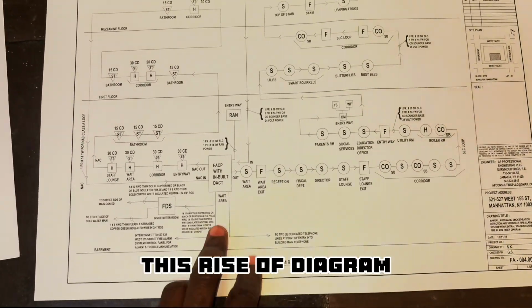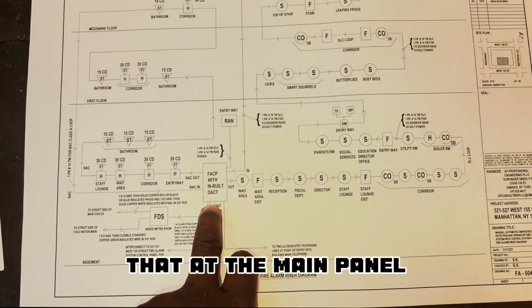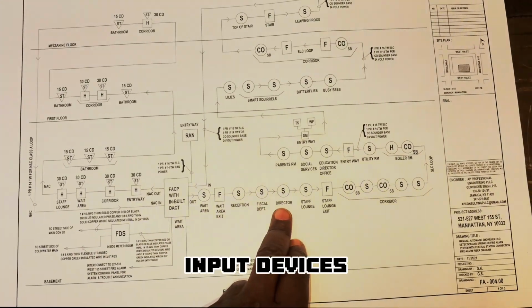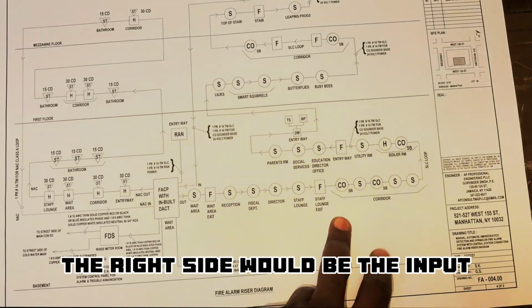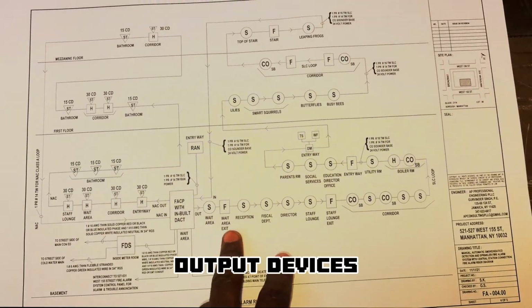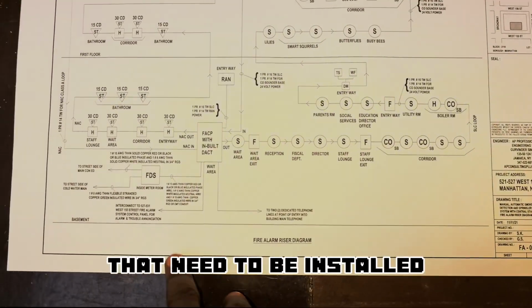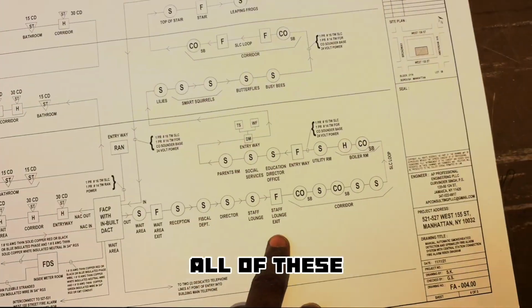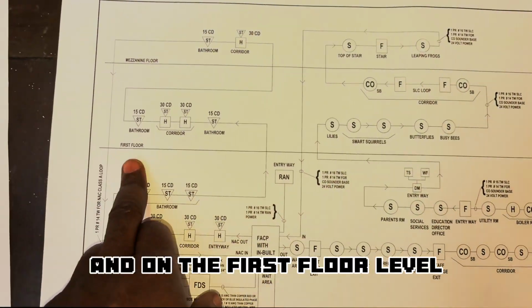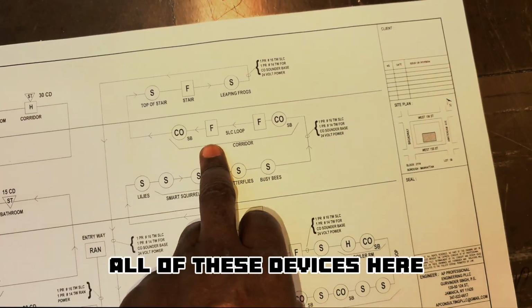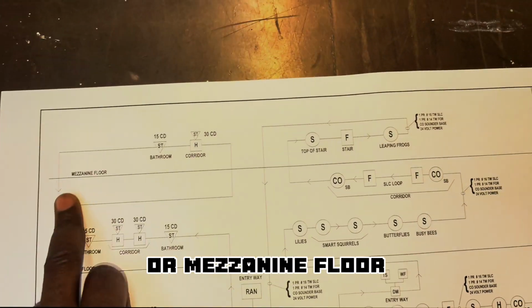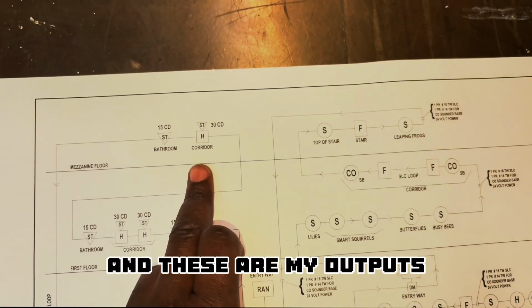So on this riser diagram, it's telling us that the main panel should have a DACT. These are all of the input devices. The right side will be the input. The left side would be the output devices. So these are all my input devices that need to be installed on the basement level. All of these devices here. And on the first floor level, all of these devices here. And on the second or mezzanine floor, these devices here, and these are my outputs.